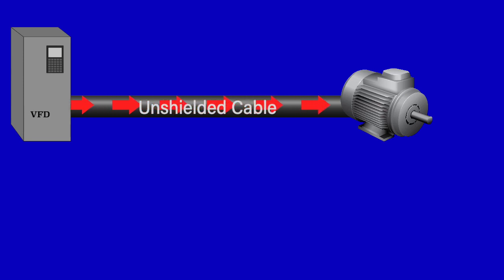According to Kirchhoff's law, the current must return to the inverter, but what path will it take to do so? This current is unlikely to return to the inverter through the cable ground. Because of its high frequency, it likes to travel on a conductor's surface and not through its cross-sectional area due to the skin effect. Cable ground wires have a small surface area compared to a common path of this current, building steel.